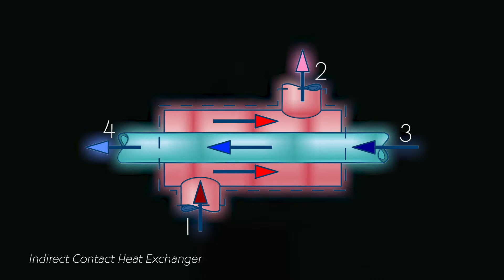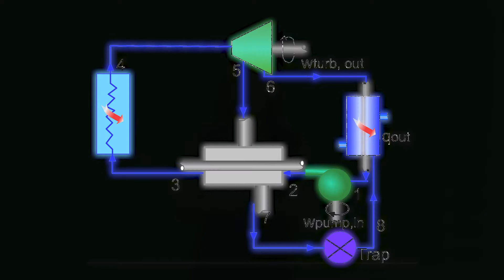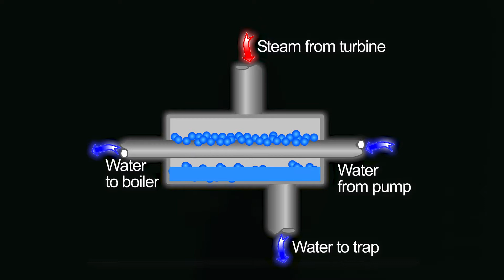An example of where you might find this is in a steam cycle, which is used to generate power. When it's used in this manner, it's called a closed feed water heater. You'll have a hot stream coming from a turbine, and you've got a cold stream going through a tube or a series of tubes. Your steam will condense over those cooling coils, and it'll condense as a liquid out the bottom, while what's going through the tube will be heated up. So that's one way to move heat around within a steam cycle.